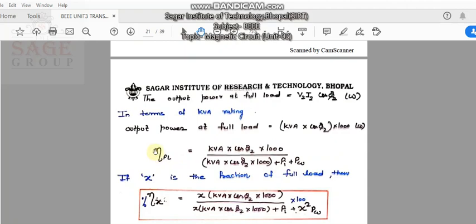Look here, this is your formula for efficiency: apparent power into cos phi 2, where cos phi 2 is the power factor of the load (secondary side), into 1000, divided by (kVA into cos phi 2 into 1000 plus Pi plus Pw), where Pi is your iron loss and Pw is your copper loss.